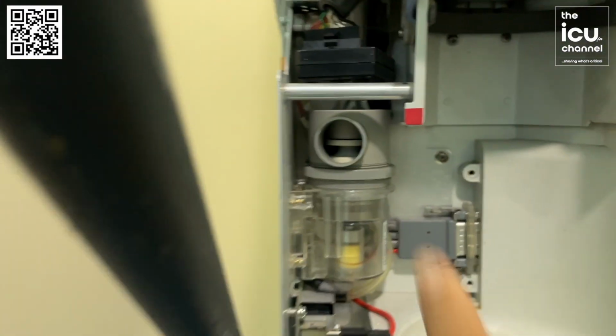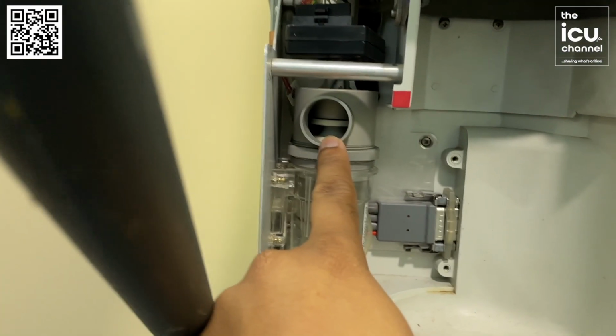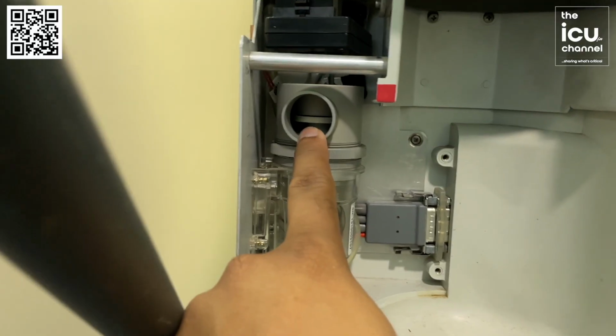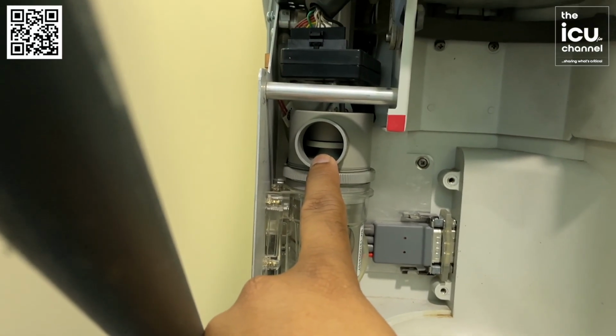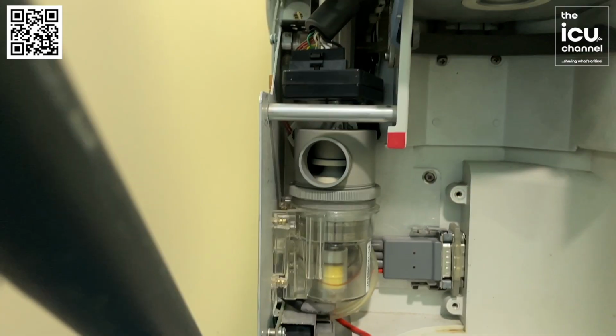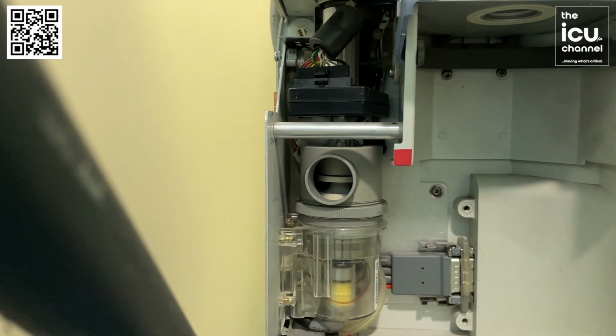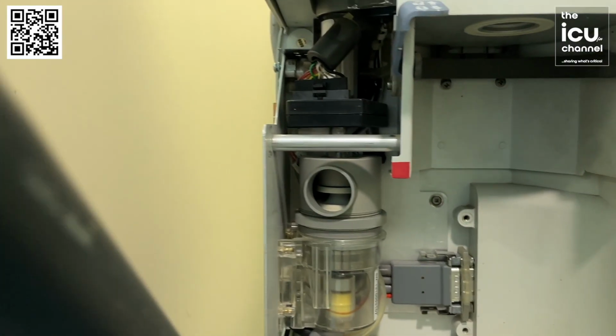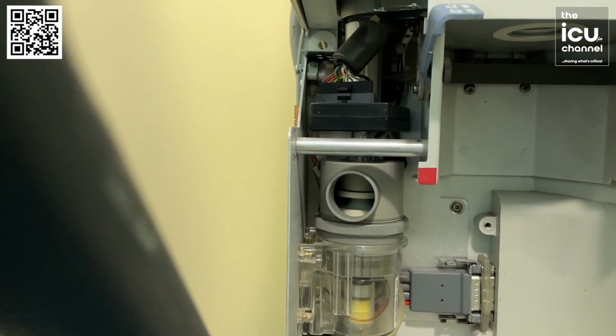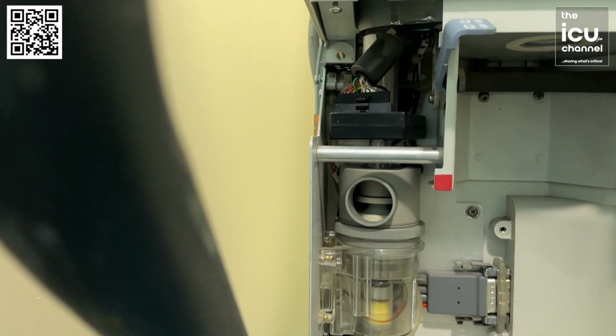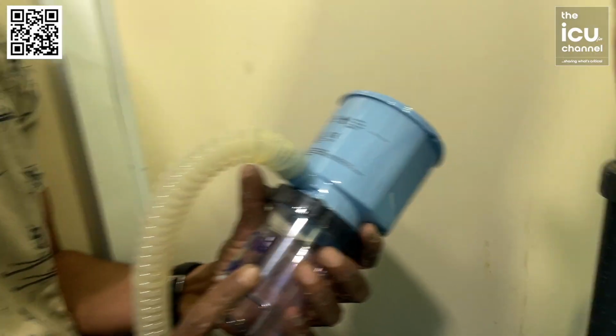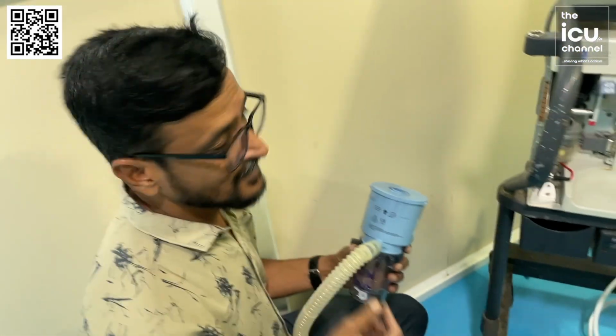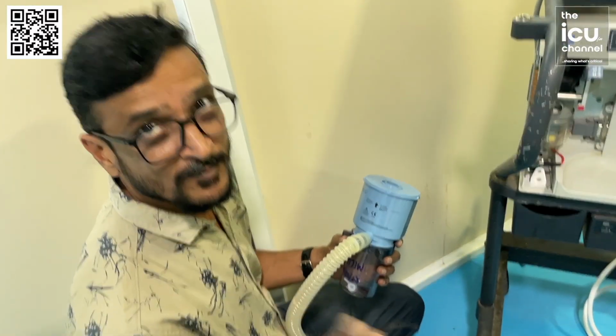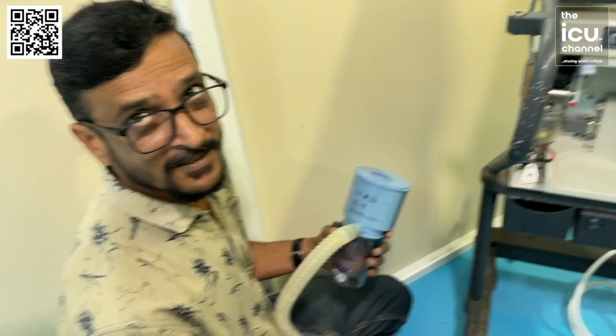And this expiratory valve is basically a leak sensor which detects the normal leak in the circuit. It will control the leak compensations, how much amount of leak can be compensated. There is some leak which can occur inside the filter or inside the circuit. Some amount of leak can be compensated.